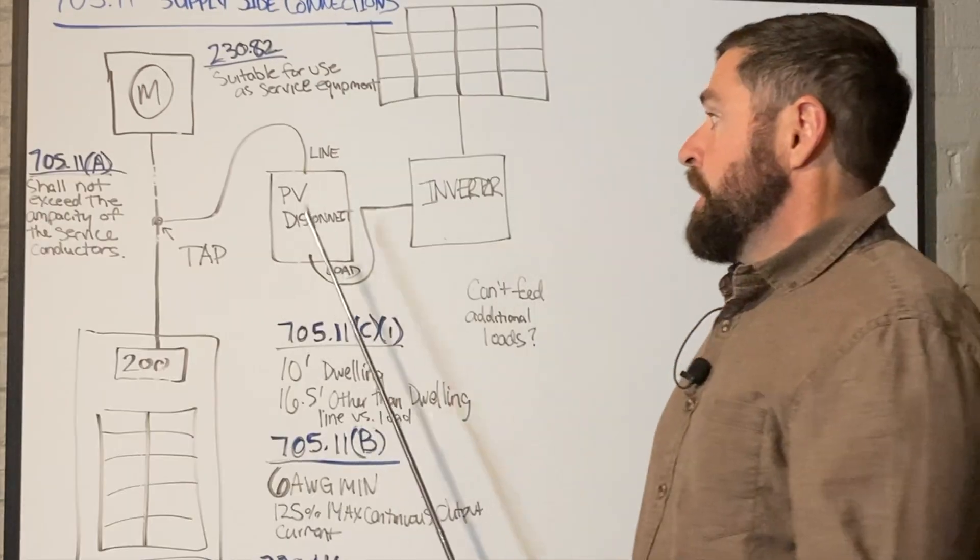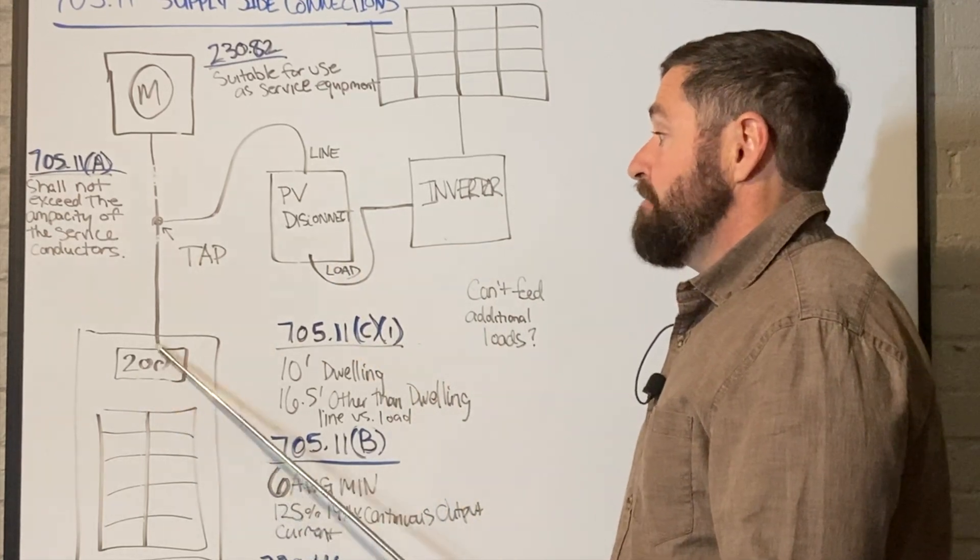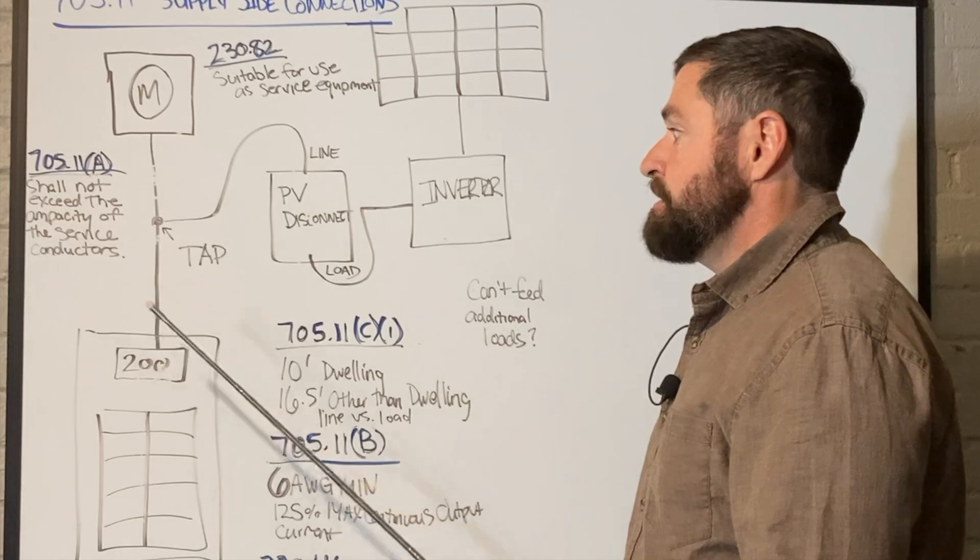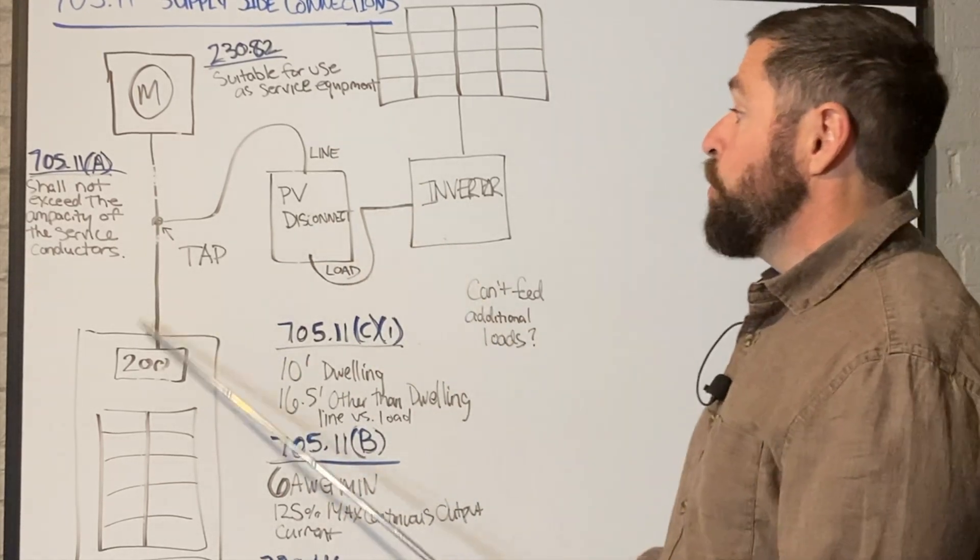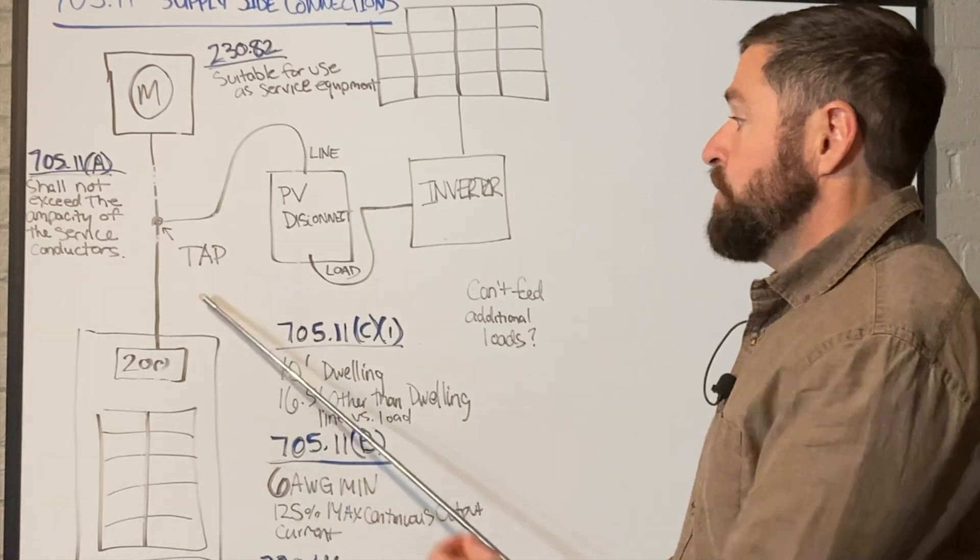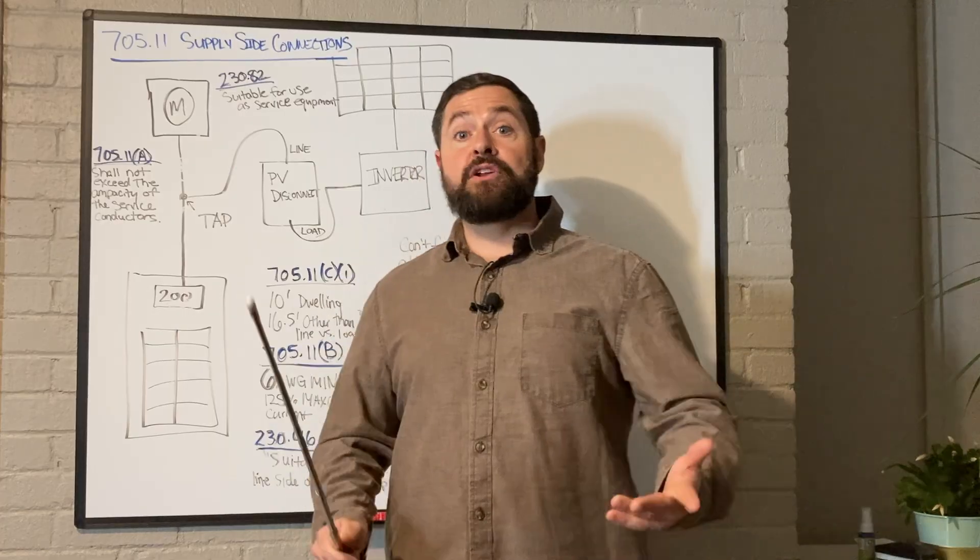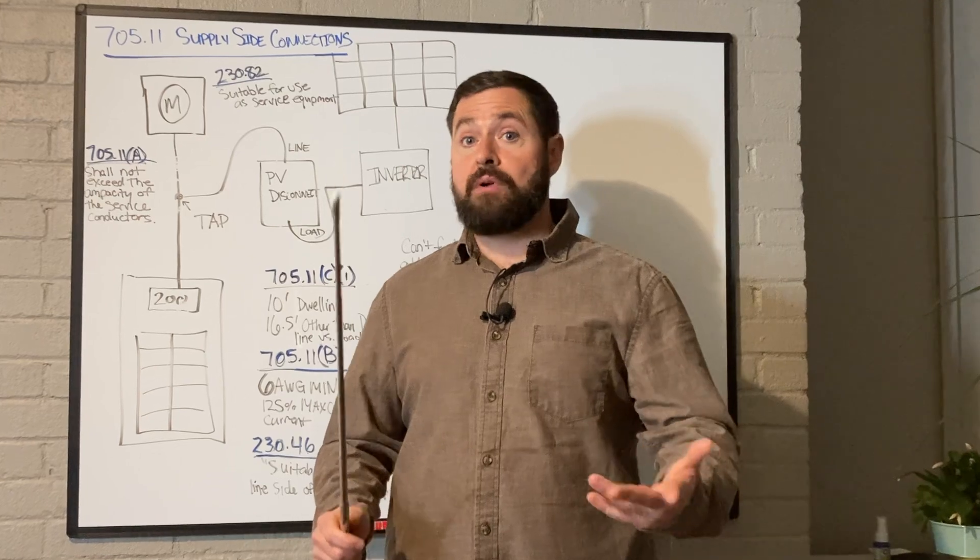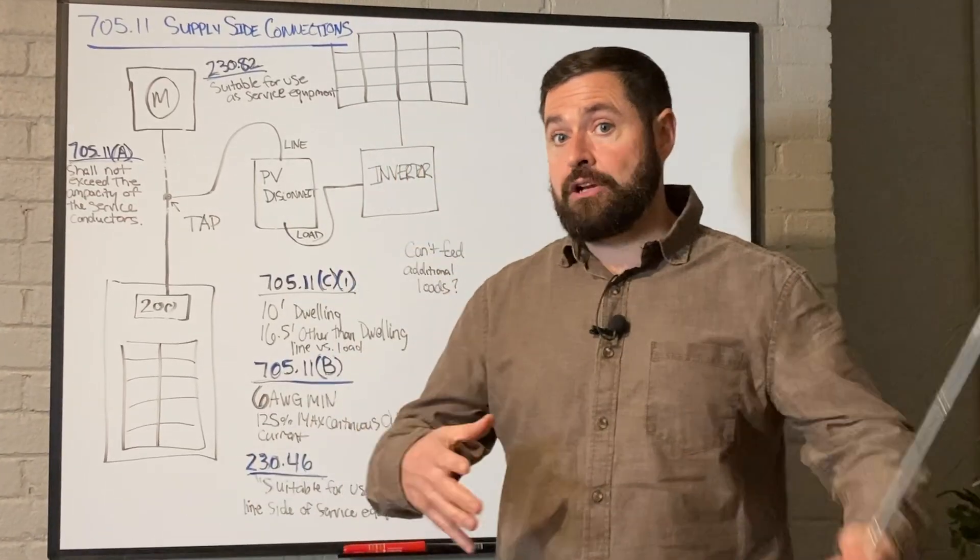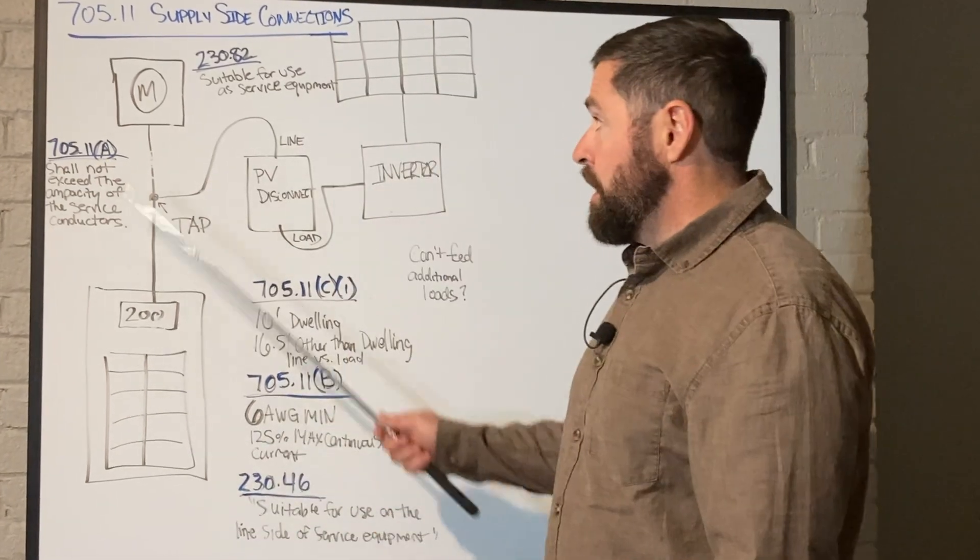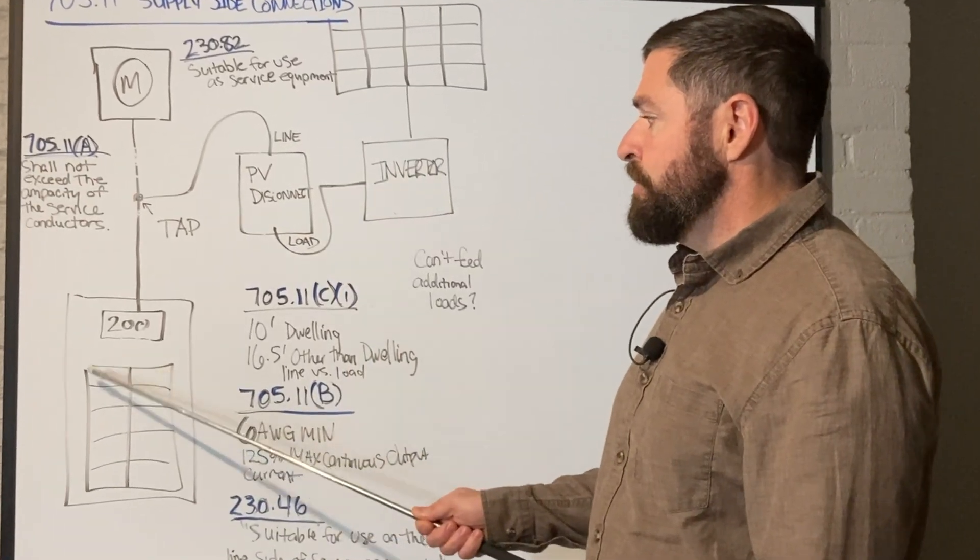Next, if you do your tap, say, inside of this panel just on the line side of the service disconnect, what you can do is you can run all four: L1, L2, neutral and ground. You keep them all separated as you know there should only ever be one neutral to ground bond in a service and that is at your service disconnecting means. So in this situation, your grounds and your neutrals would be bonded in here and then anything downstream would stay unbonded.